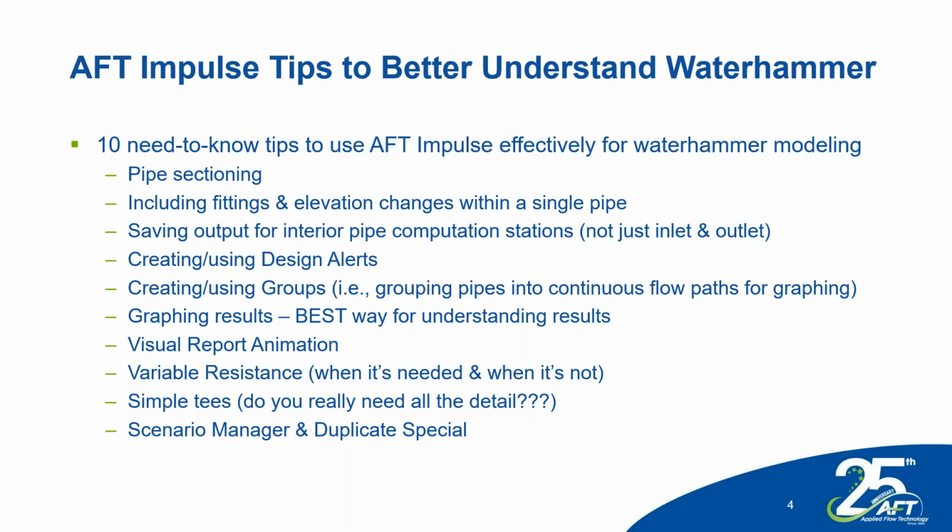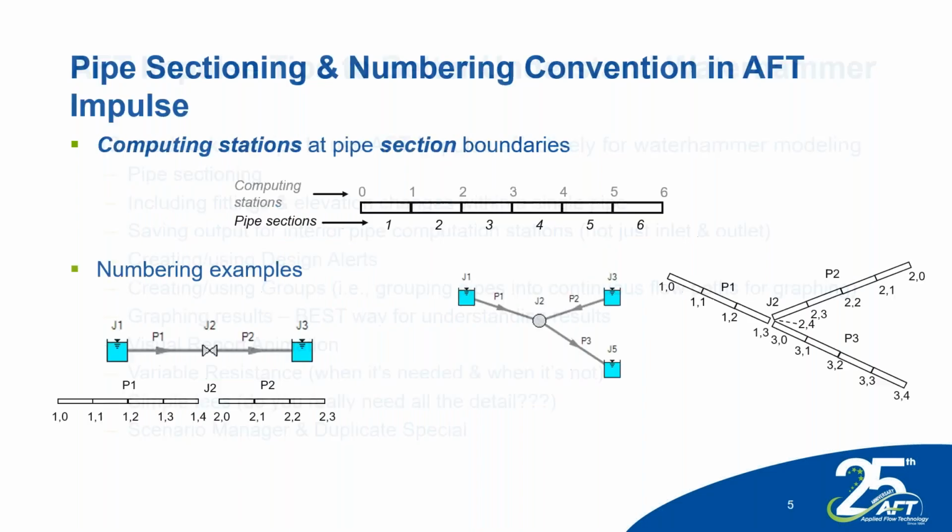So let's say that you're not sure how fast you should close your valve. Well, if you use either duplicate special or the scenario manager, you can easily try different closure mechanisms. Half a second, 1 second, 2 seconds. And that way you can compare the results a lot easier and know which method you need to go with. So I'll show you both of those tools today.